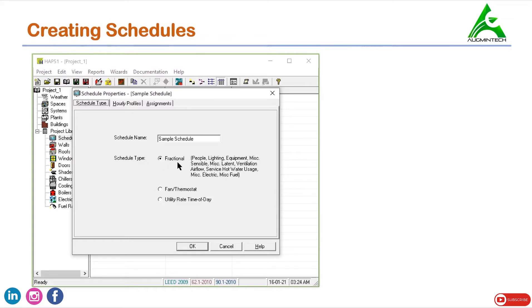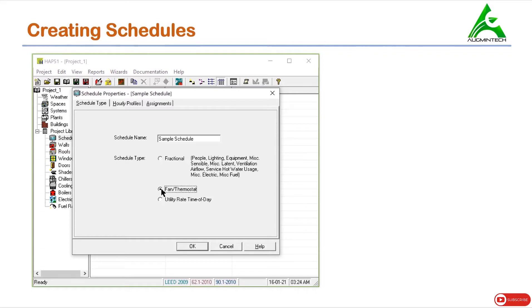The schedule type can be fractional or it can be binary like fan or utility rate. The fractional value means the number of people present in any conditioned space can vary between 0 to 100%. The lights and equipment used — some of them might be working at any given point of time and some are not. The schedule for fan or utility rate is defined in a binary manner; the fan can be switched on or switched off. So let's go ahead and create a schedule for people. First we need to name it — let's say the schedule for people.